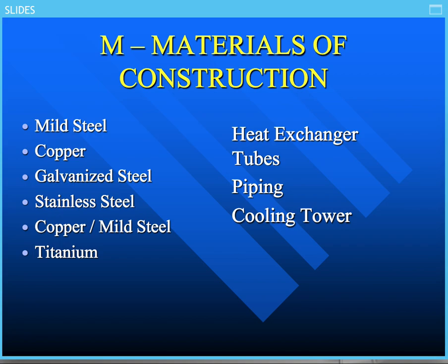are mainly metals, because that's what we're dealing with in regard to corrosion problems. So we're dealing with mild steel particularly, which is sensitive. That could be the piping, it could be heat exchanger tubes, and it could be copper. The galvanized steel is not normally tubes in a heat exchanger, but it is a part of a cooling tower. Stainless steel can be, of course, part of the cooling tower. It could be a plate and frame heat exchanger. So consequently, these are the things we have to look for in your cooling water system.